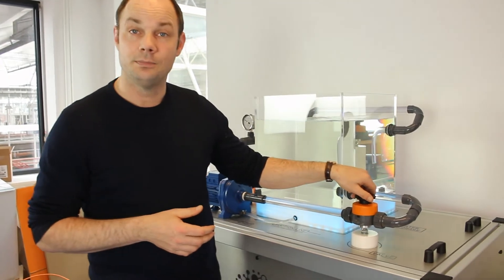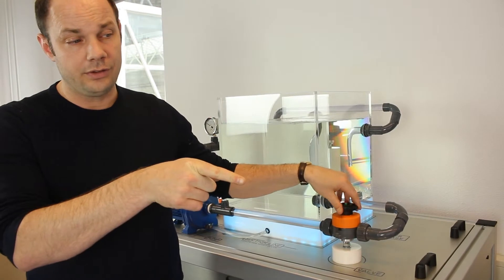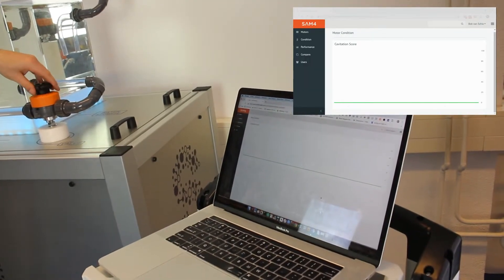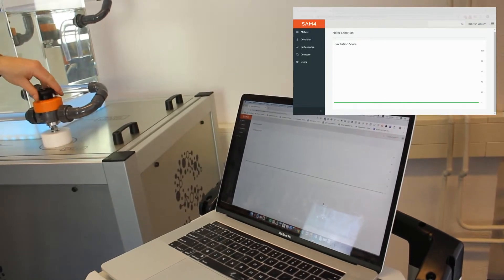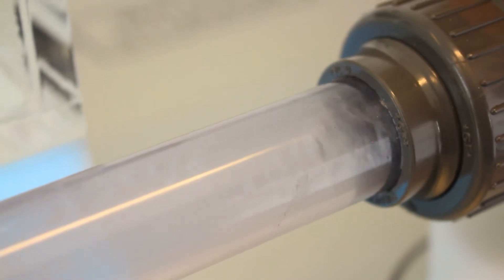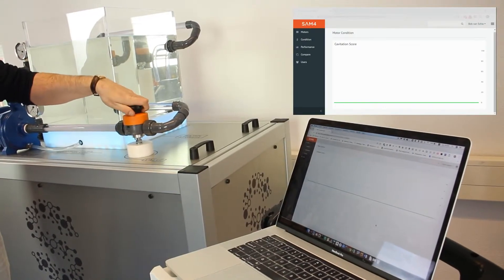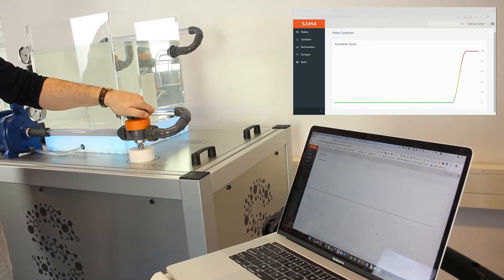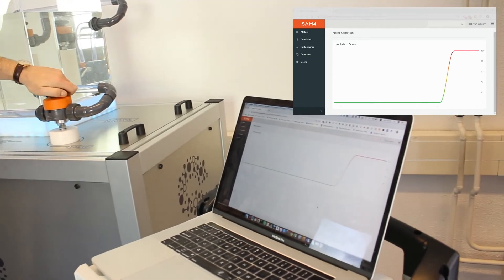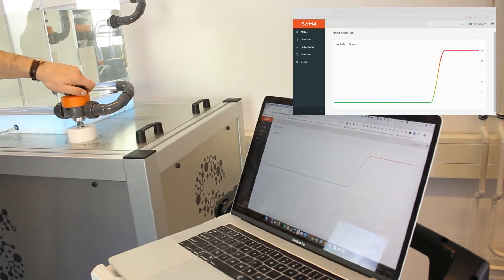Let me show you how. I'm starting to introduce cavitation here, and if you look at the cavitation score on our dashboard you'll see it's green — and green means good. But now, as you can hear, cavitation is being introduced, and with a slight delay you'll see the cavitation score rise. There you go.